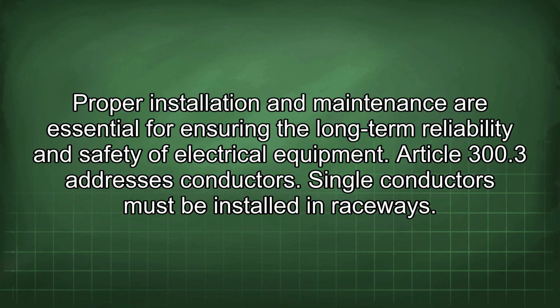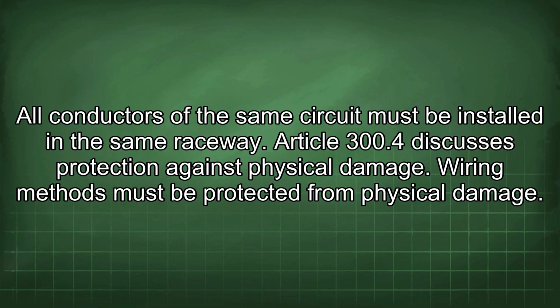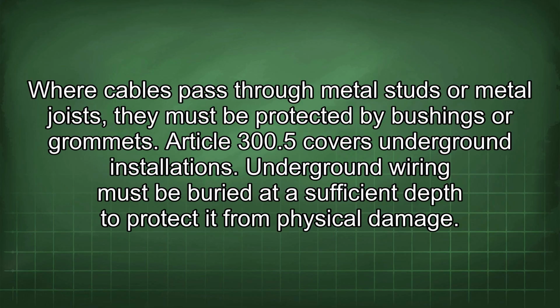Article 300.3 addresses conductors. Single conductors must be installed in raceways. All conductors of the same circuit must be installed in the same raceway. Article 300.4 discusses protection against physical damage. Wiring methods must be protected from physical damage. Where cables pass through metal studs or metal joists, they must be protected by bushings or grommets.